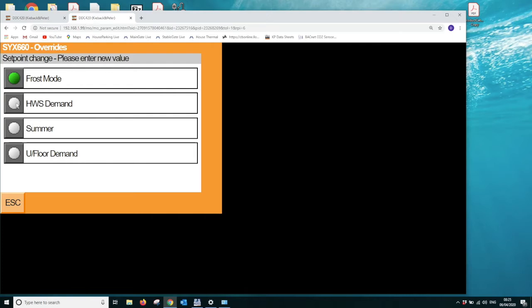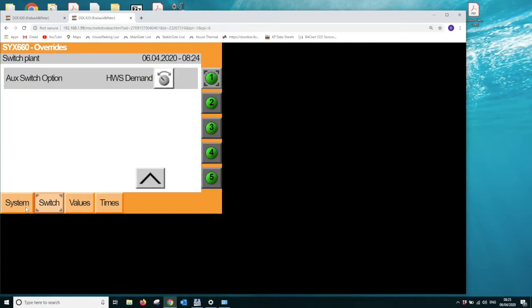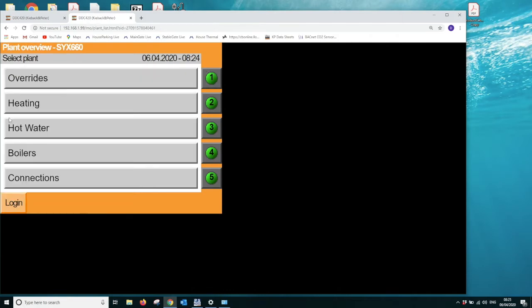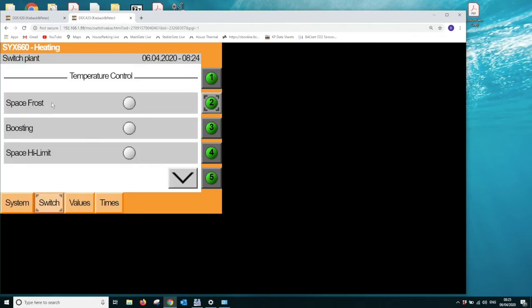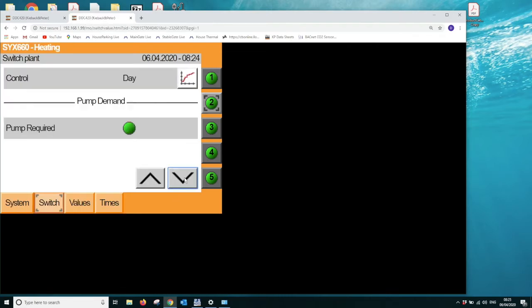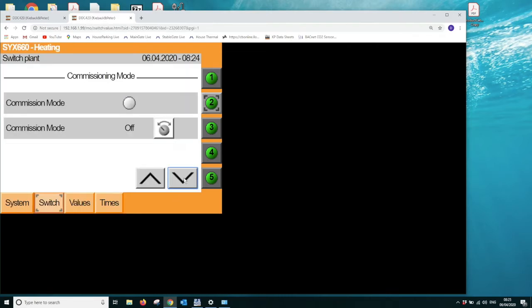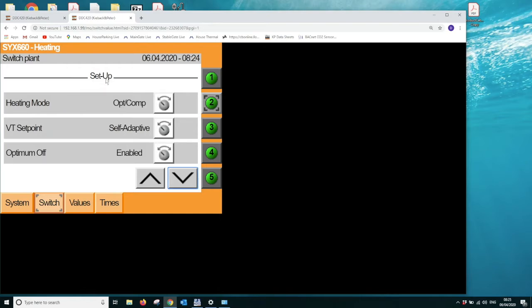Okay, so we're going to select hot water demand. Okay, and those are the two options which are in the override menu. So I'm going to go back now onto system, and now I'm going to choose heating. So I'm going to tab down again, find the setup mode, and we can see that the default operation for the heating system is optimizer compensator.